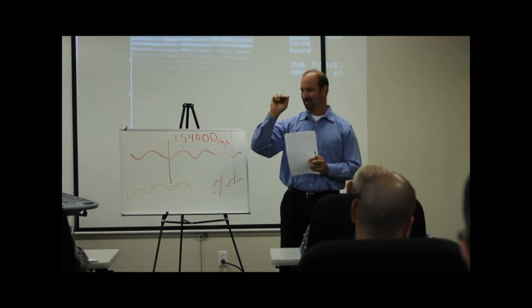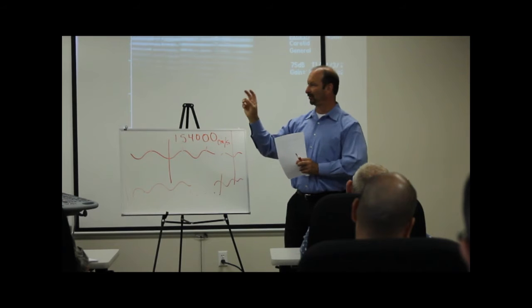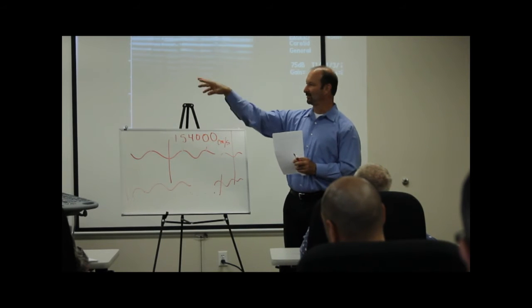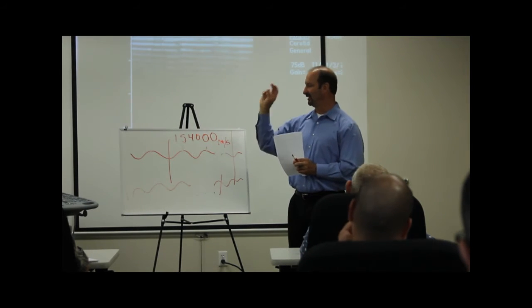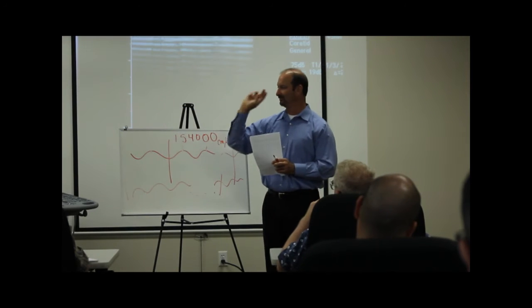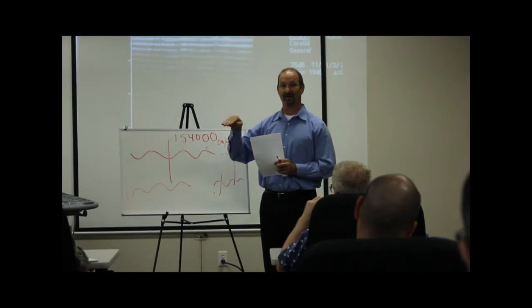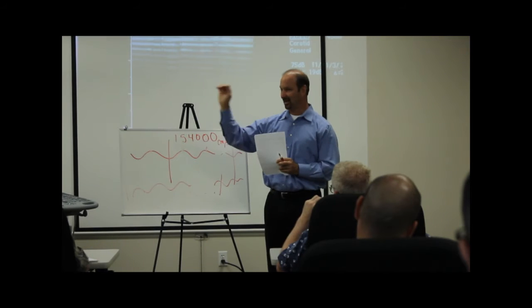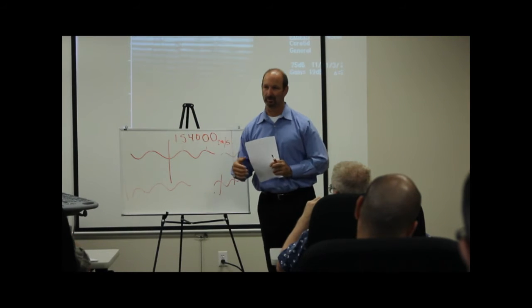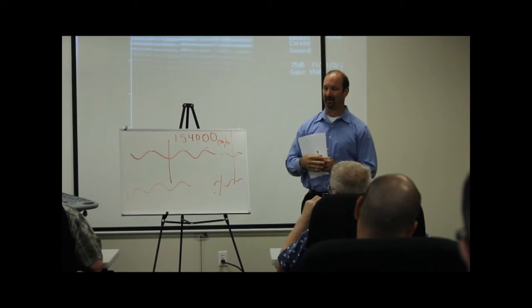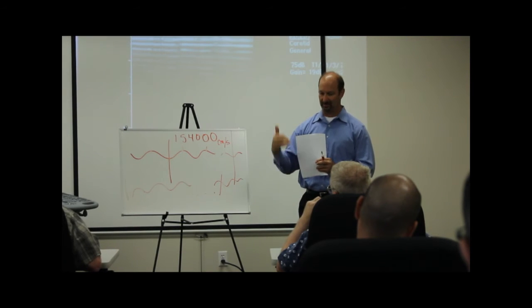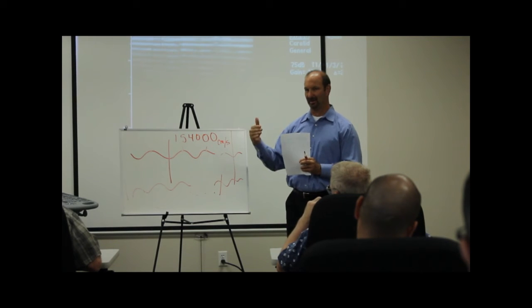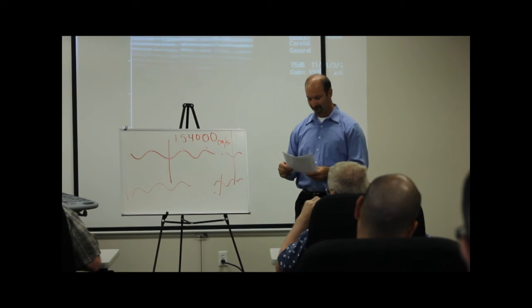Remember, that sound has to go out. If I've got a little ball right here, it only comes back to me if I hit it on a flat surface. If I bounced it off the top of that podium, it would hit that, go off that way, and never come back. That's how sound is. It's got to come right back to me. So only about 2% of the signal comes back. That's why it's important for that machine to be putting out the appropriate amount of power that it's set to, so that it can get as much information back.